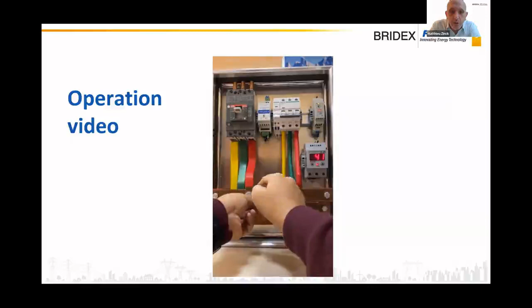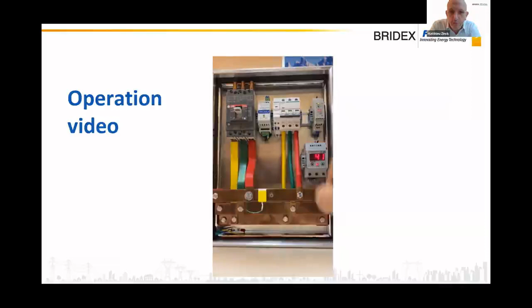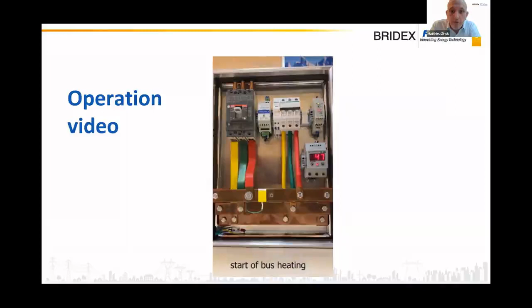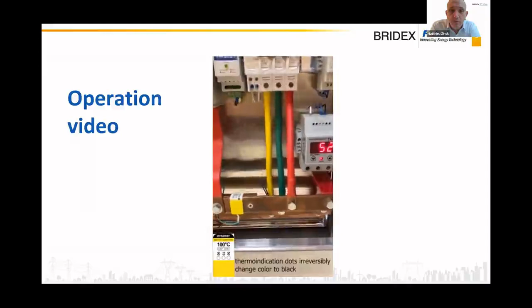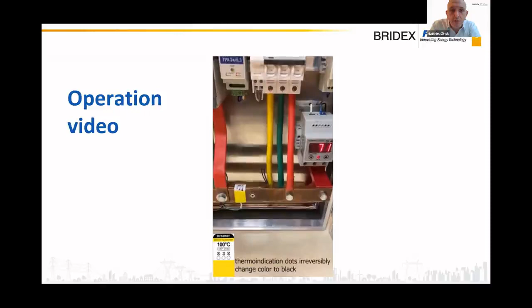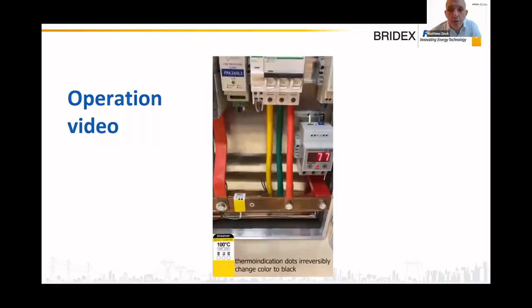And my colleague is basically setting a sticker on the bus bar. He's not completely wrapping it around because for the sake of the demonstration, we don't need to. And here he's turning on the breaker. That is basically turning on the heating element, and you see the temperature increasing. So now we are reaching 50 degrees and the first thermodot has turned black. And so we're waiting now for 70 degrees for the second thermodot to turn black and indicate that we have reached this temperature. And so the temperature will increase up to 100 degrees.